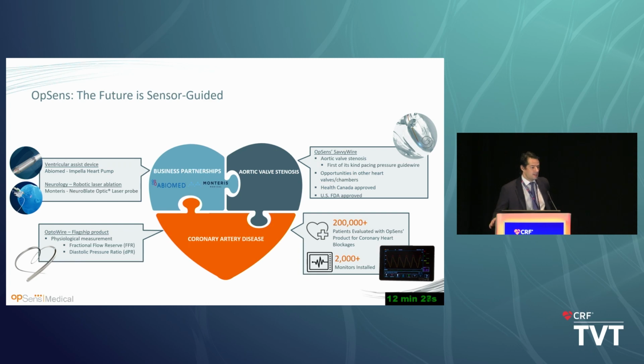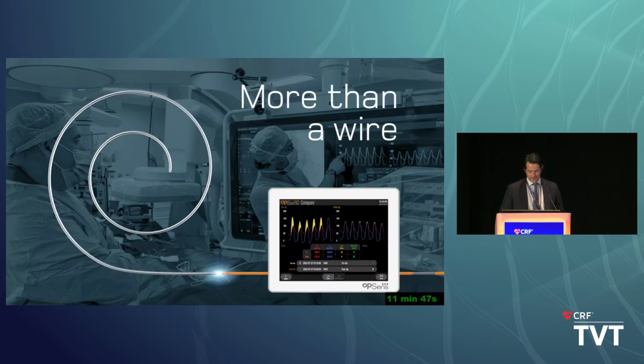And then their new kid is the SavvyWire, where they leverage their Fidela sensor and put it on the SavvyWire to design really the third generation TAVI wire, dedicated for TAVI, safer, good stiffness, but also with the capacity to LV pace, so insulation that allows you to pace, and also a sensor on the tip on the LV side to give you the gradient continuously during the case. They did more than 200,000 cases in coronaries and more than 2,000 with the SavvyWire already. So really a company based around sensors.